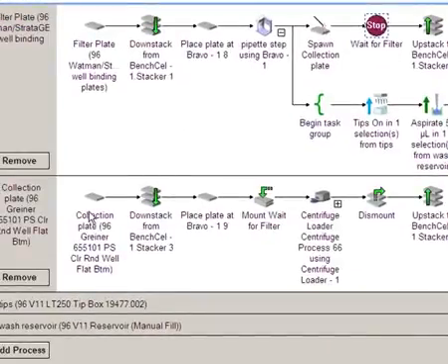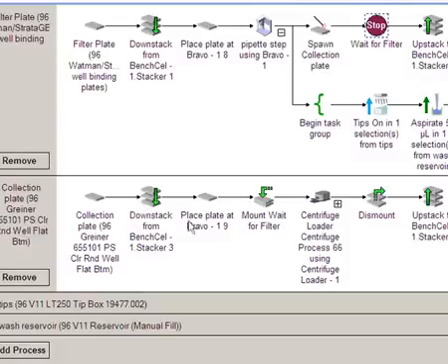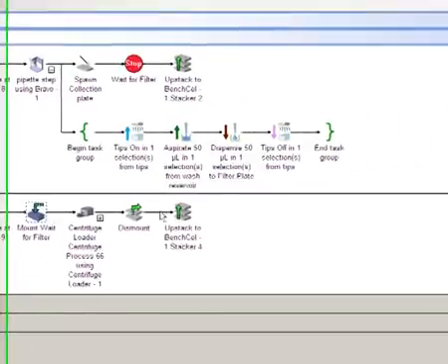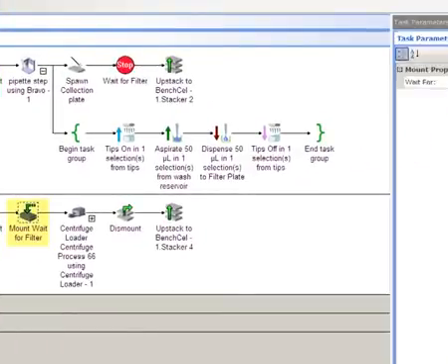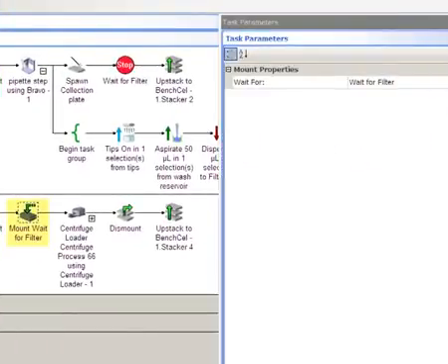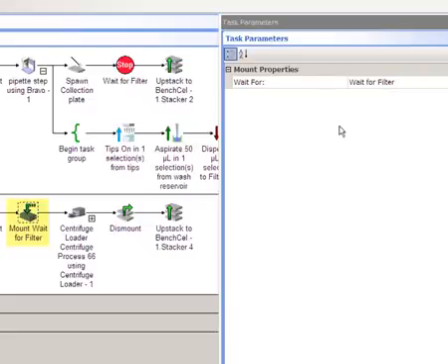The collection plate process is held back until it is spawned. At that point, the collection plate down stacks from the specified bench cell stacker and moves to Bravo Deck location 9. Now it's ready to be mounted, but by which Labware? In the task parameters area, notice that I selected wait for filter. This is the reference to the wait for task in the filter plate process.